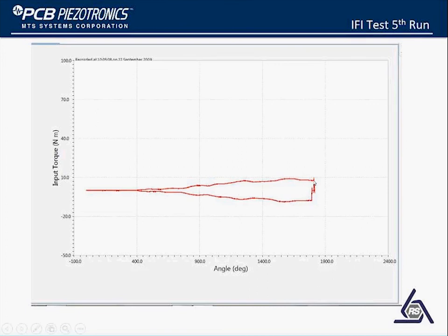We're just taking it up to the verge of clamp load and then backing off. So again, what we're going to be looking for is in this first turn, after we have backed it off, we're going to be looking for our minimum and our maximum off.